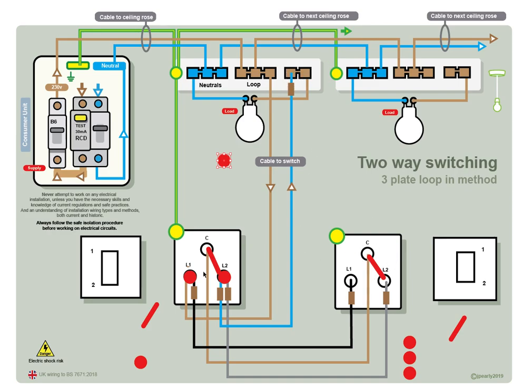So now we know that we can switch it on from here, we can switch it off from here. So what we want to do: we walk back to this switch again, you want to switch it back on again. So we'll flip the switch again, let's see what happens. So from the rose, we come into L1, L1 goes up to common, common goes to common in the second switch, down L2. It's on L2. Generally L2 means it's going to get back to the ceiling rose. L2, yep there we go, L2 up to the ceiling rose, and the switch is made. There we go, so light is on.